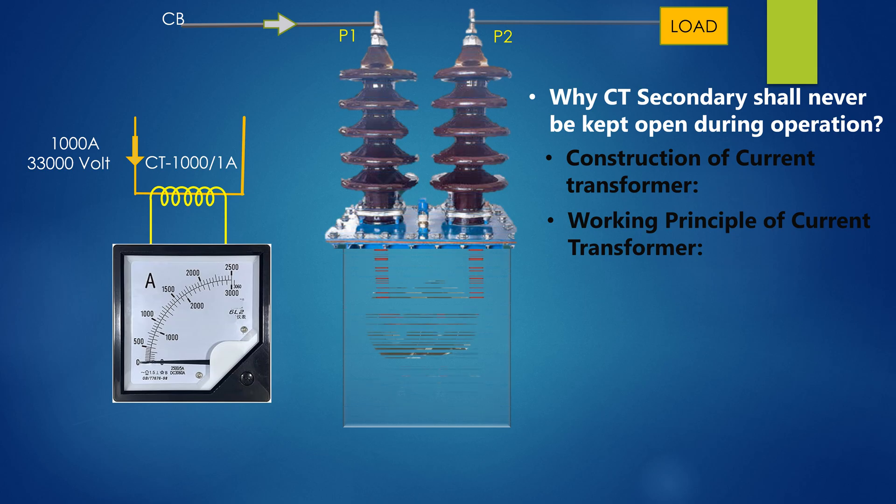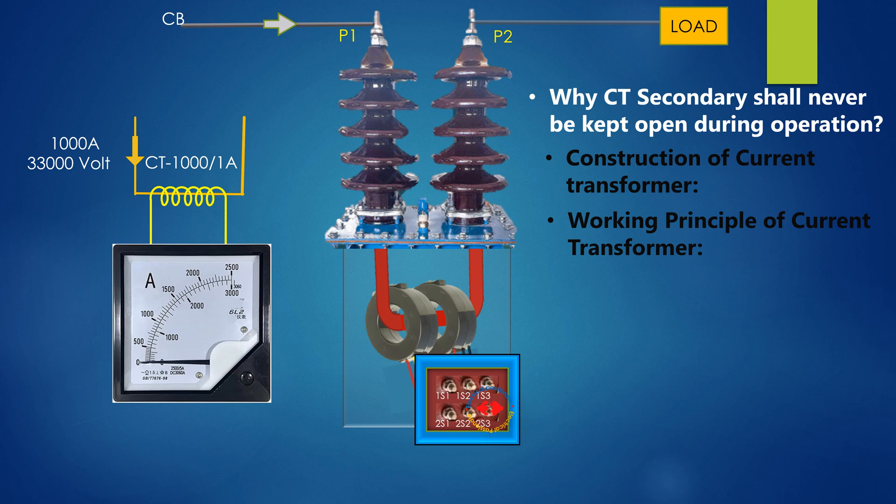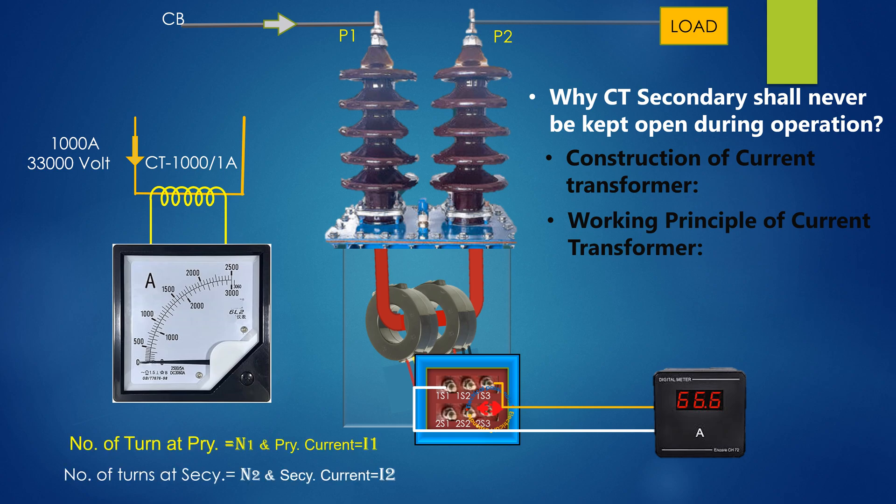Here, the current transformer consists of two round type cores upon which secondary windings of many turns is wound and primary windings of single turn passes through the core. The primary windings of the transformer is connected in series with the load and carries the actual current to the load. The secondary winding of the CT is connected to a measuring device and ammeter. The number of secondary turns is proportional to the current flowing through the primary. That is, the larger the magnitude of primary current, the greater the number of secondary turns, which in turns lower the secondary current.